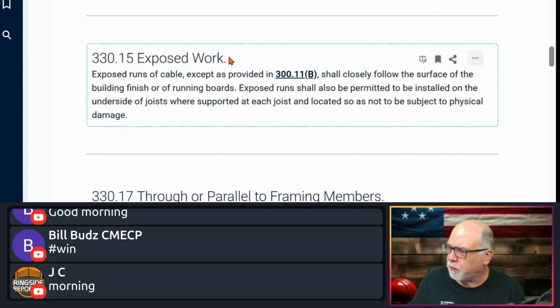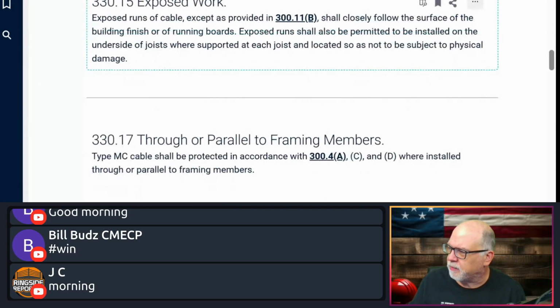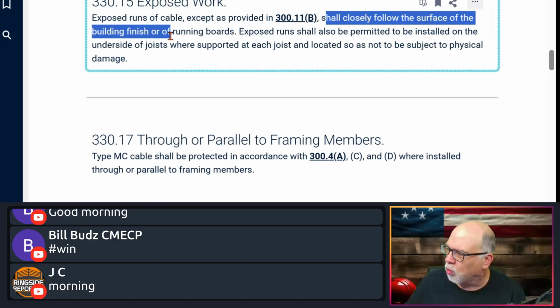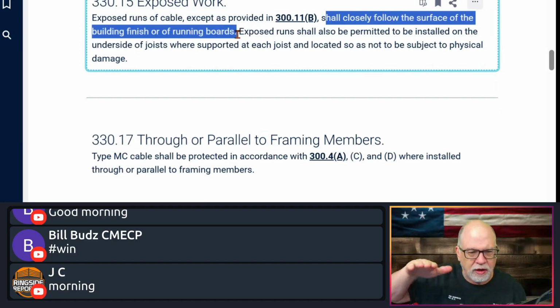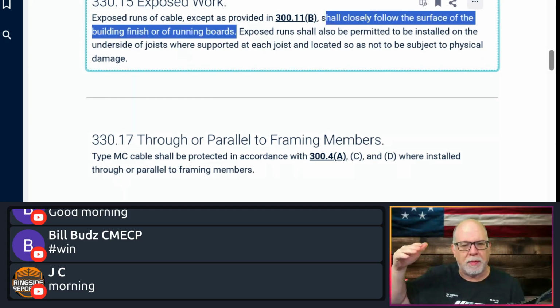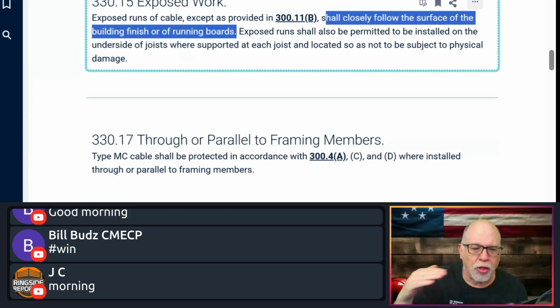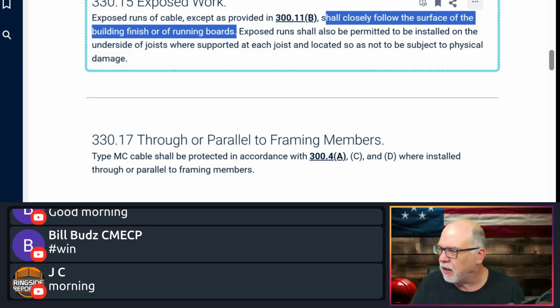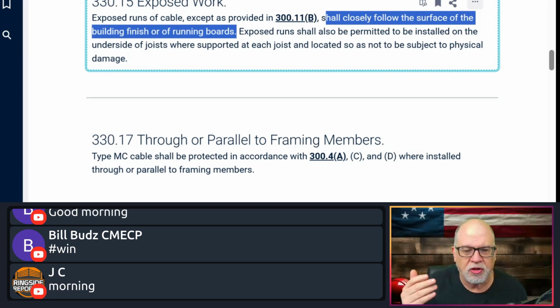That's fine. Exposed work. Exposed runs of cable except as provided in 300.11(B). That is, again, above suspended ceilings. We looked at that a second ago. It says it shall closely follow the surface of the building finish or run on running boards. So again, unless you're going across the support structures or being supported by guide wires, or you're running it from framing member to framing member or through framing members, other than that, it runs close with the building finish, or you'd have to run it on running boards. We don't want it to droop. We don't want to put any undue stress at terminations. Again, obviously, the bigger the MC, the bigger the worry, right?